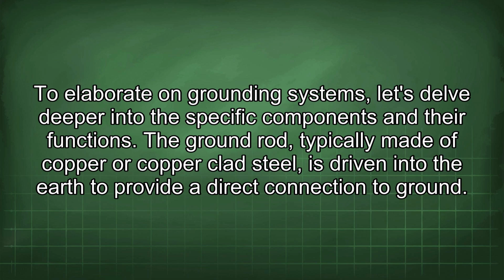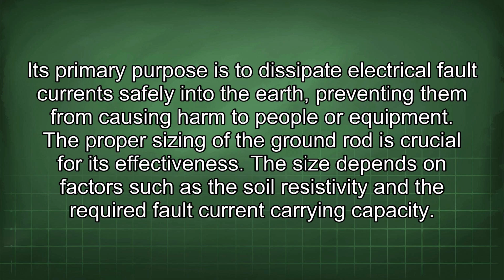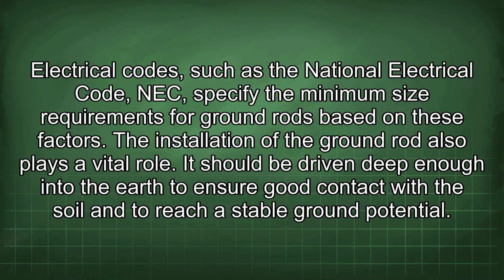The ground rod, typically made of copper or copper-clad steel, is driven into the earth to provide a direct connection to ground. Its primary purpose is to dissipate electrical fault currents safely into the earth, preventing them from causing harm to people or equipment. The proper sizing of the ground rod is crucial for its effectiveness. The size depends on factors such as the soil resistivity and the required fault current carrying capacity. Electrical codes, such as the National Electrical Code, NEC, specify the minimum size requirements for ground rods based on these factors. The installation of the ground rod also plays a vital role.